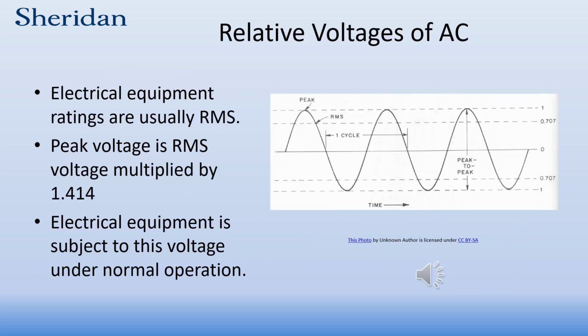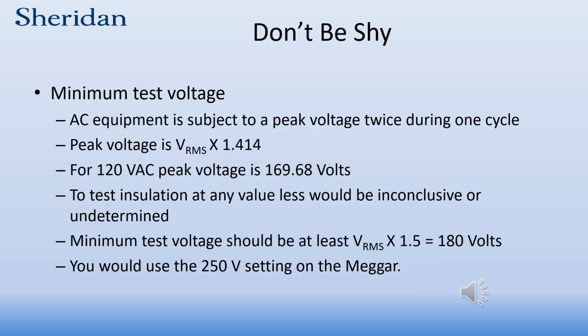Let's look at the voltage that electrical equipment is subject to. Electrical equipment is usually rated in RMS voltage, which is less than peak voltage. You can obtain peak voltage by taking the RMS voltage and multiplying it by 1.414, which is the reciprocal of 0.707. Electrical equipment under normal operation sees this voltage, which is much higher than RMS. If we look at a piece of equipment rated for 120 volts AC, the peak voltage is very close to 170 volts.